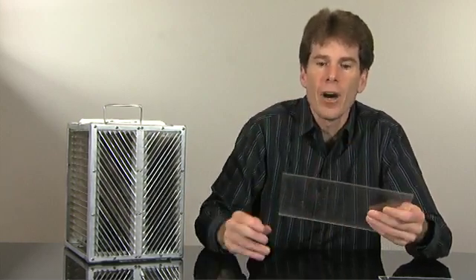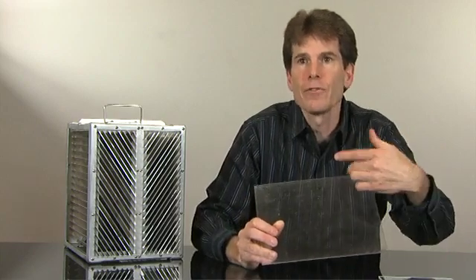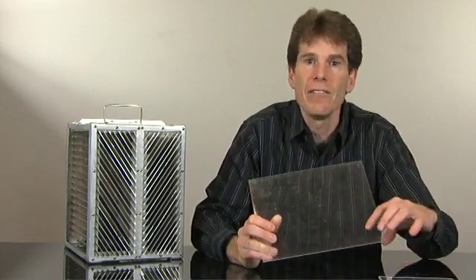Or a configuration this way, if you can see it, where the flow comes in and downflow, you have problems. The upflow creates problems for solids dropping back and fouling. If you have a downflow design where your flow is coming in, down and out, solids do process but the oils fight against the flow, creating issues.